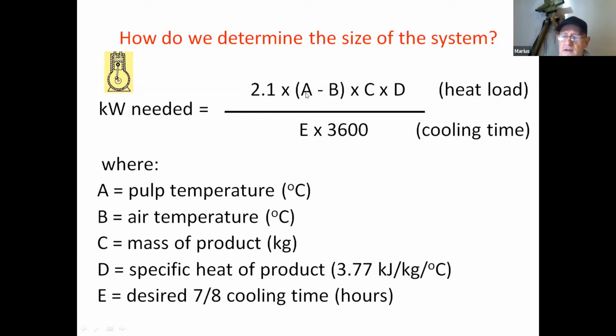If the fruit comes in at 30 or 40 degrees, this numerator is a lot bigger. If my cooling time remains constant, then obviously dividing a bigger numerator by the same denominator is going to give me a much bigger requirement in terms of the kilowatts required. So the heat load is a lot bigger. The cooling time is the same, so obviously the system needs to be bigger. The other factors of importance there, obviously the air temperature, because the colder you want to deliver, the more impact that's going to have there.